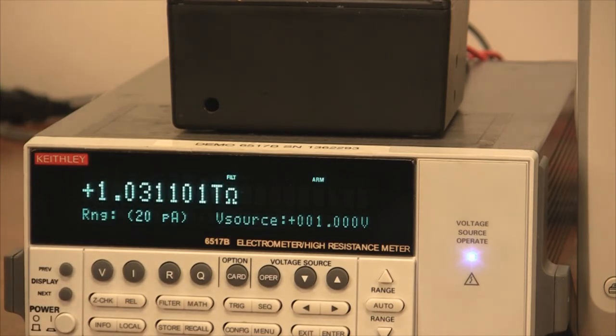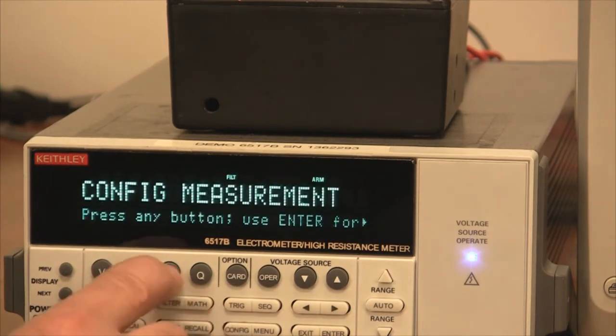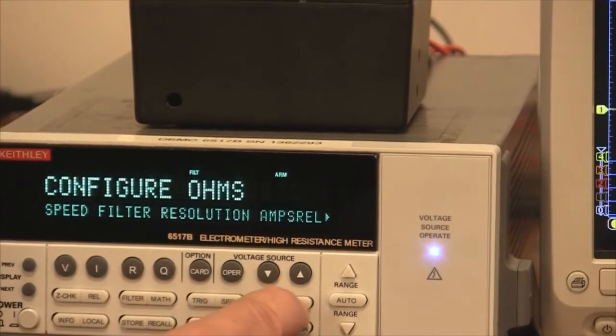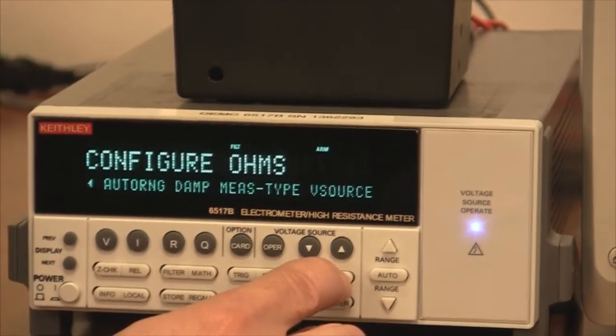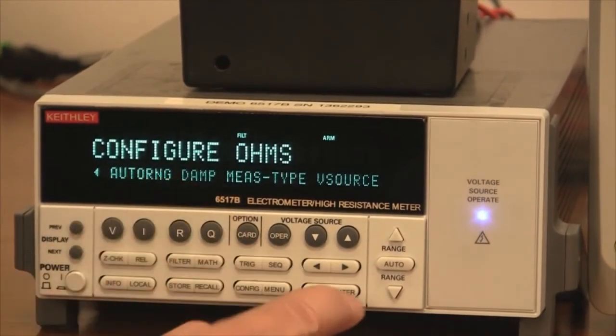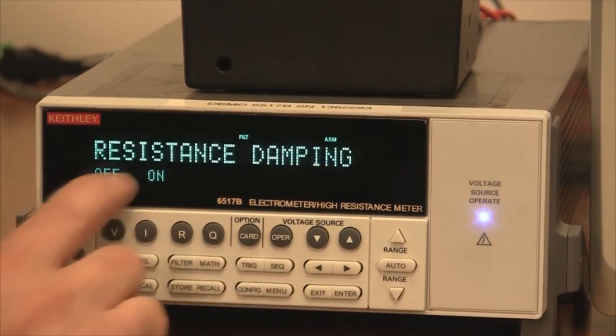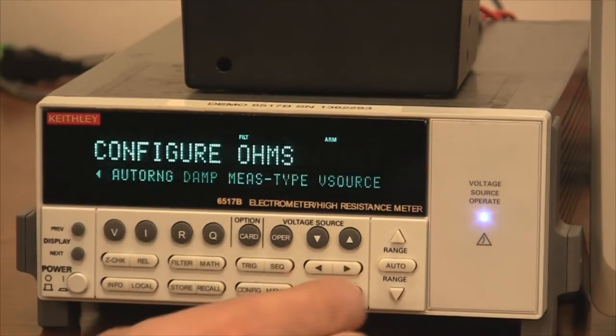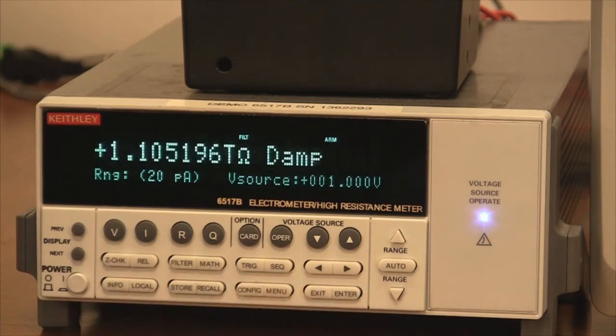One other thing we can do to add on to this for stability on these high resistance measurements is a feature that Keithley has called damping. And damping is sort of a filter, but much better. If we were to hit configure R, go to damp, hit enter, we want to turn it on, exit.